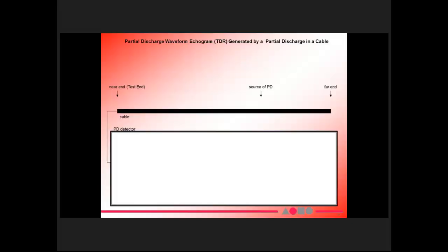All right, so let's look at the partial discharge waveform and how it's generated. So what we have over here, we have a cable. This is the near end where we hooked up the PD detector. We have the far end over here. We have the source of the PD in the cable over here. So this is the length of the cable from A to B. We're measuring at point A with our detector, and so let's see what happens if we get PD in the cable. So PD discharge occurs. The transient travels out in two directions. One hits the far end over here. The other one comes in towards us and hits our equipment, which triggers the equipment just like a normal oscilloscope, and that's what we see.